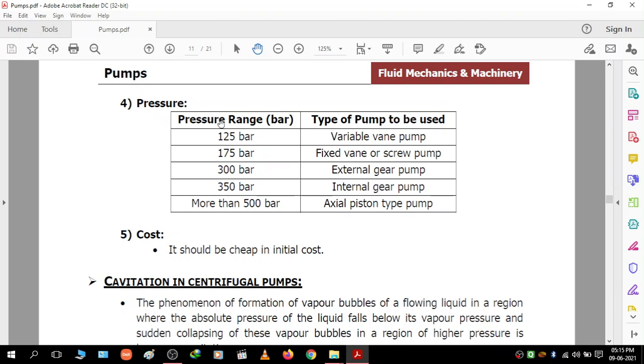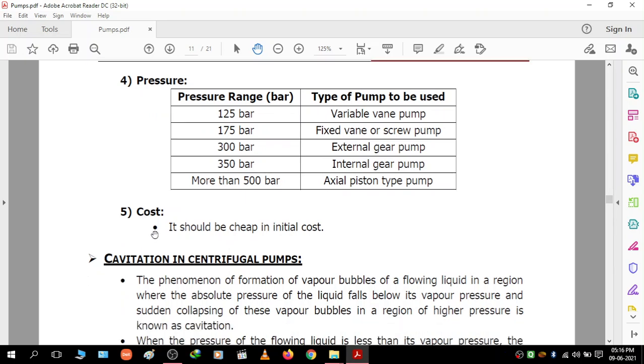Selection based on pressure range: variable vane pumps for 125 bar, fixed vane or screw pumps for 175 bar, external gear pumps for 300 bar, internal gear pumps for 350 bar, and axial piston pumps for more than 500 bar. Cost is also a consideration when selecting a pump. This is all about the selection of pump.